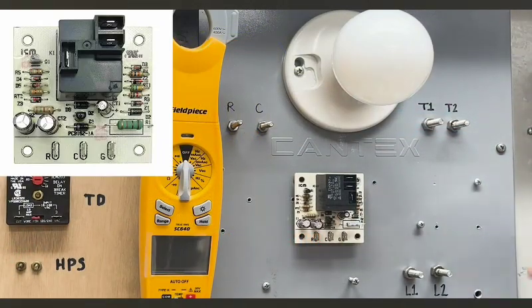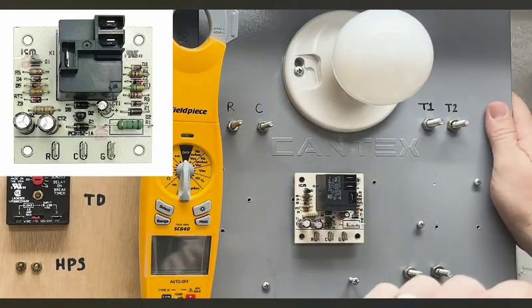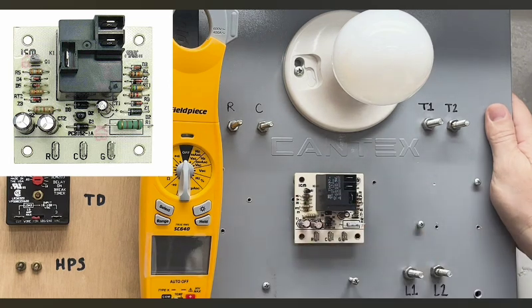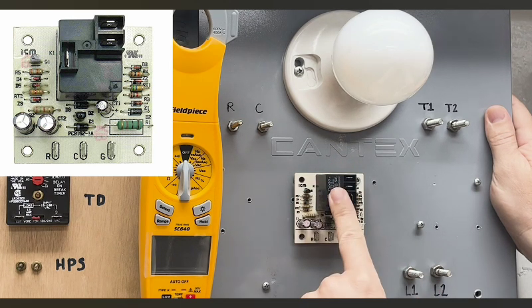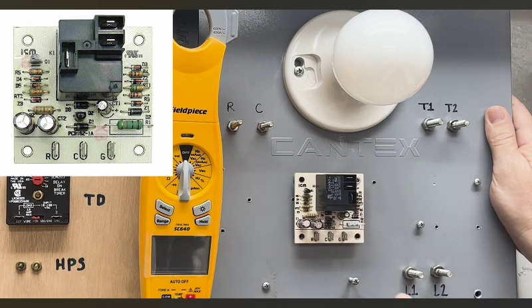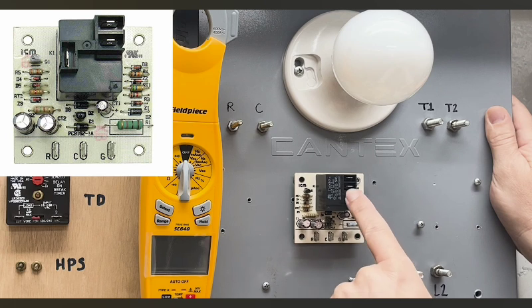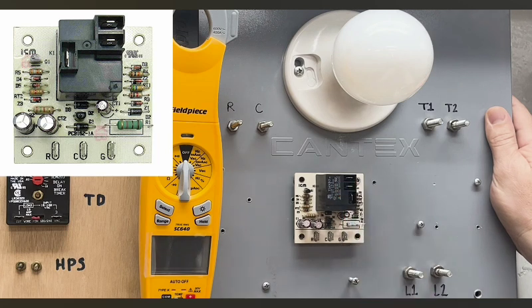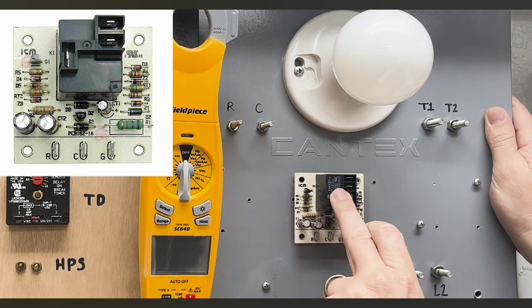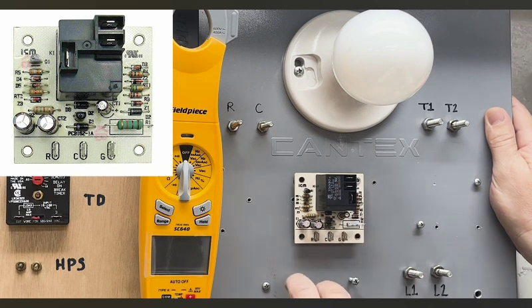Today we're going to talk about the ICM 255 blower board relay. So this is a blower control board. As you can see here, the circuit board, and the black square that's on here is the relay. We have 3 terminals on this relay. We have the common, which is your input voltage, and then we have 2 different outputs. We have a normally open and a normally closed. I'm going to demonstrate both of these while I toggle 24 volts for the blower control board to toggle the relay for normally open or normally closed.